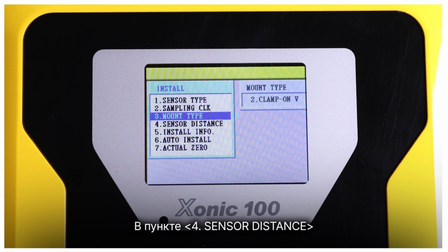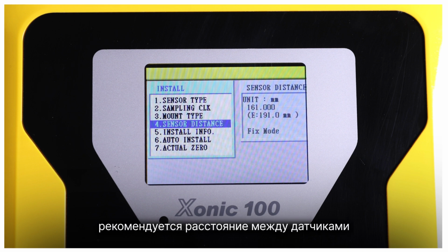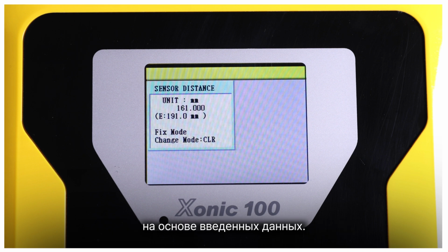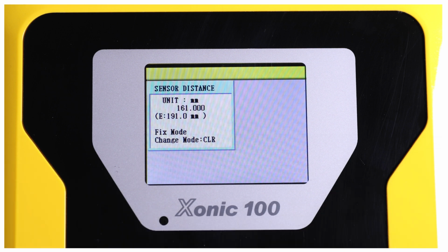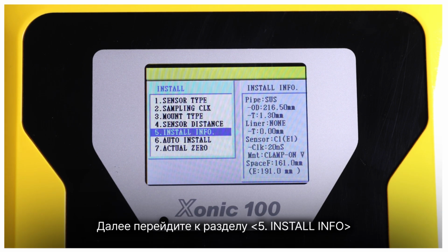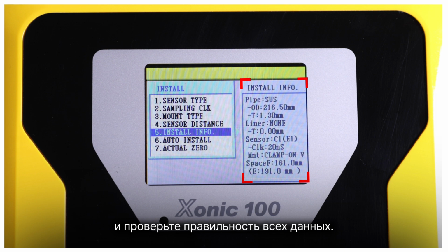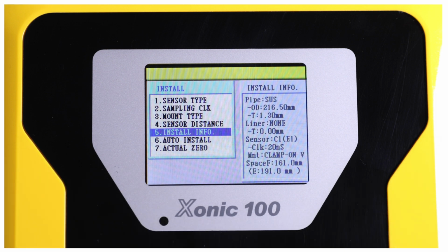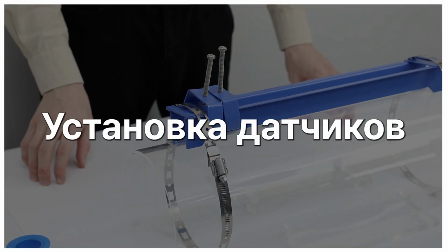At 4, Sensor distance. The distance between the transducers is recommended based on the data input. Next, move to 5, Install Info, and check if all the data is correct. Now we'll install the transducers according to the distance recommended by the flow computer.